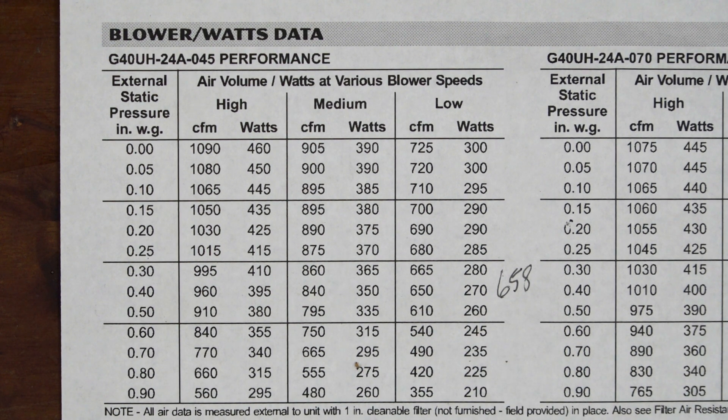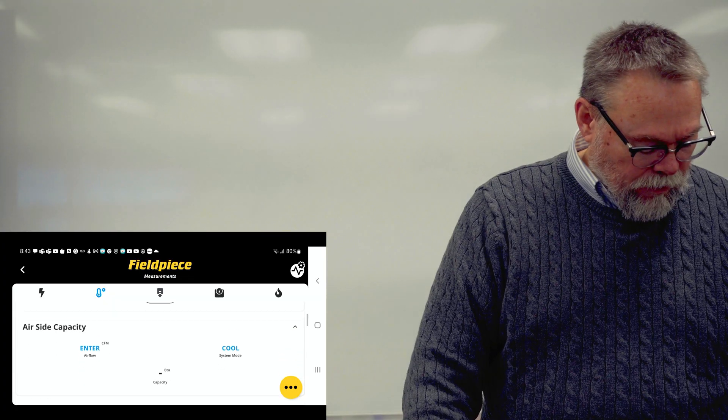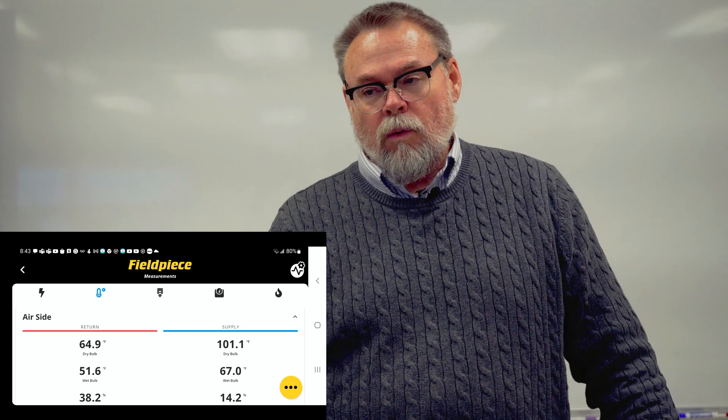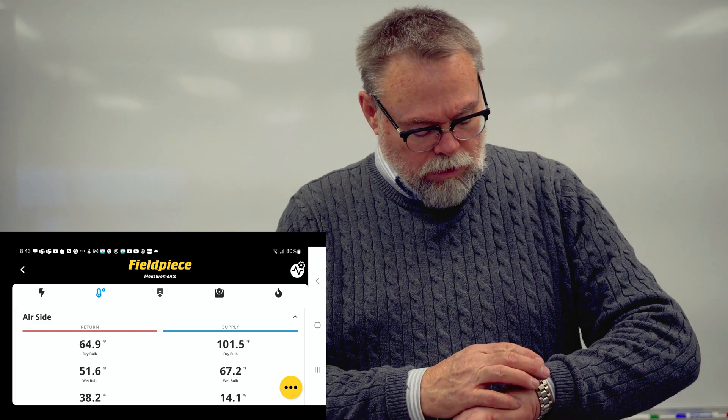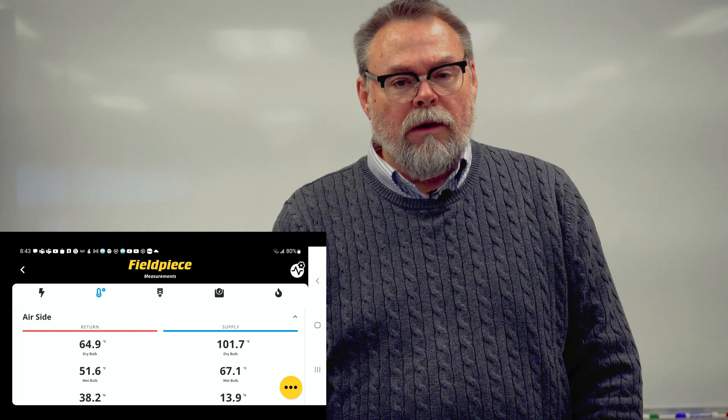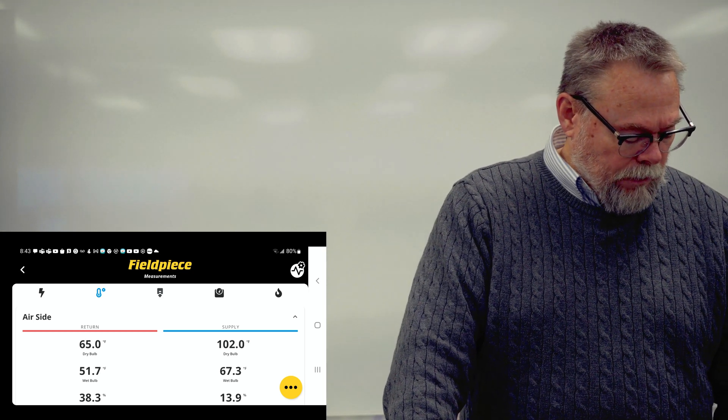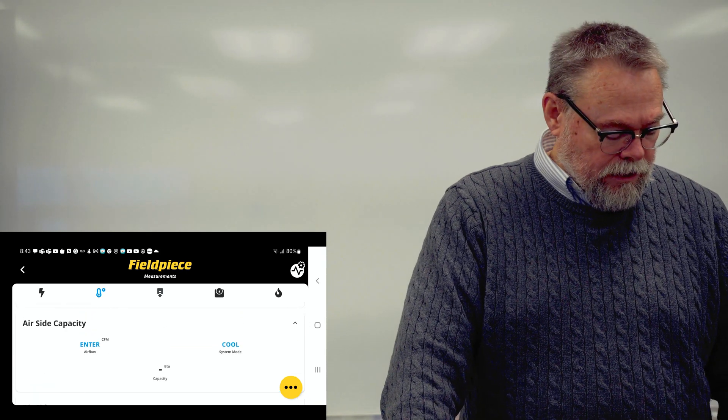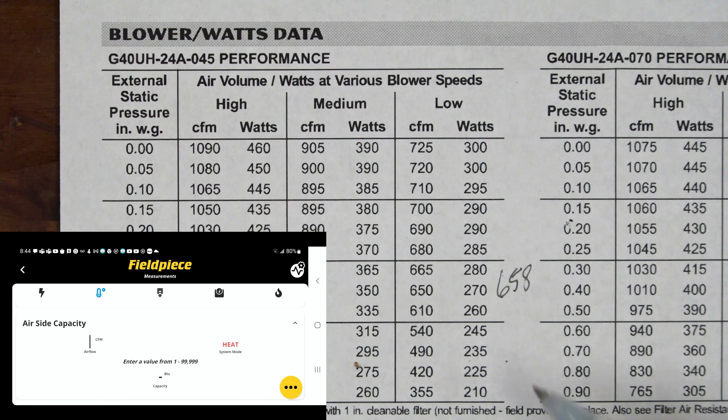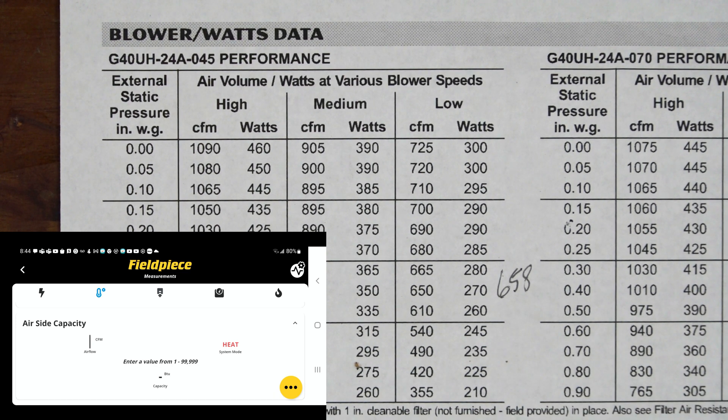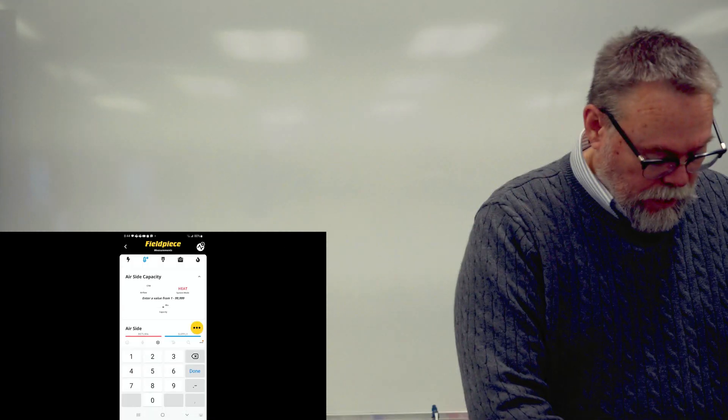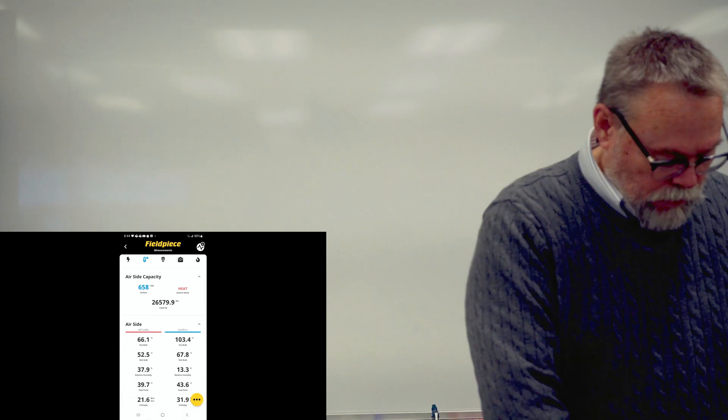Now I've already got my field piece probes in. As you can see, our return air temperature is at 65 and our supply air temperature is already at 101 and it's rising. This unit has been running, we'll run it for about 10 minutes. It's been running about a minute right now. Because I have this in cool mode on my JobLink app, I'm going to switch it over to heat. Now that it's in heat, I'm going to enter the CFM and we decided we were going to use 658. So 658, just put that in there.